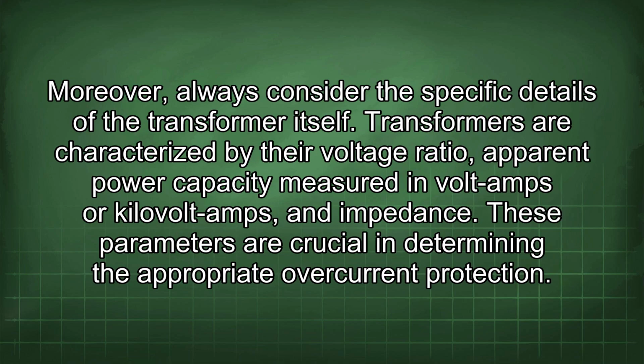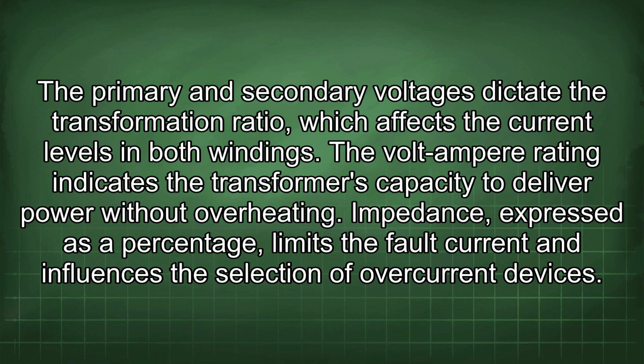Moreover, always consider the specific details of the transformer itself. Transformers are characterized by their voltage ratio, apparent power capacity measured in volt-amps or kilovolt-amps, and impedance. These parameters are crucial in determining the appropriate overcurrent protection. The primary and secondary voltages dictate the transformation ratio, which affects the current levels in both windings. The volt-ampere rating indicates the transformer's capacity to deliver power without overheating. Impedance, expressed as a percentage, limits the fault current and influences the selection of overcurrent devices.